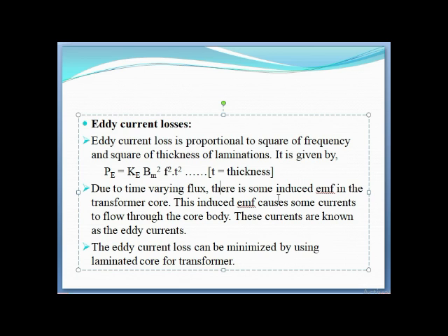Due to time-varying flux, there is some induced EMF in the transformer core. This induced EMF causes some current to flow through the core body. These currents are known as eddy currents. A laminated core reduces these eddy currents so that the current flow and eddy current losses are minimized.